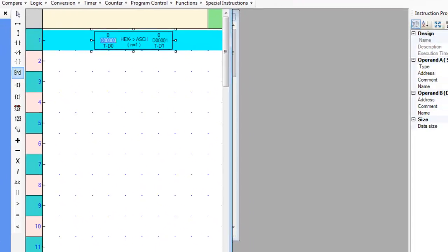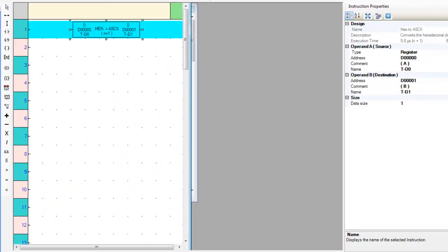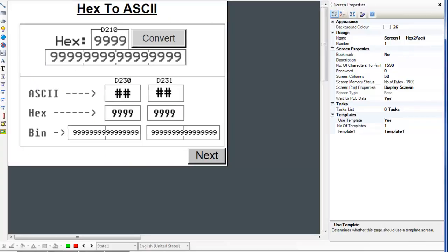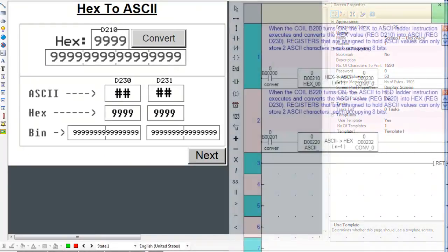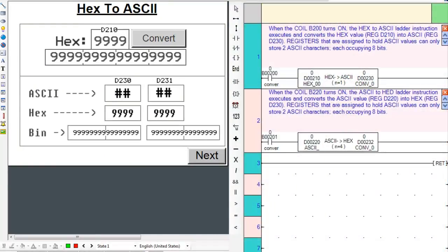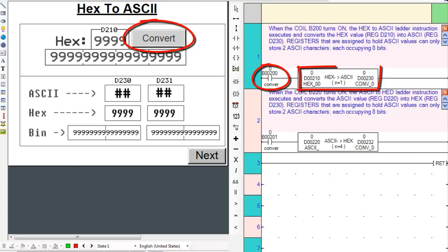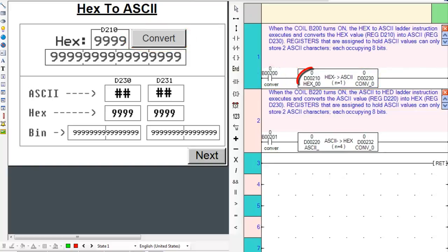let's go over to screen number 1 and place the appropriate ladder logic subroutine on the right of the screen. Notice the subroutine. When the B200 coil turns on, the Hex to ASCII ladder instruction executes and converts the Hex value from operand A and places the equivalent ASCII value in operand B.